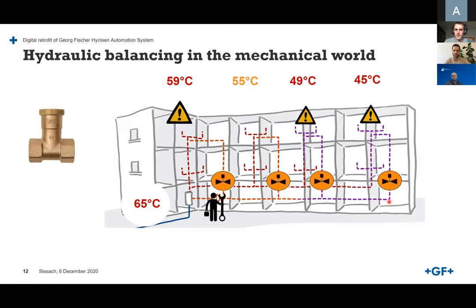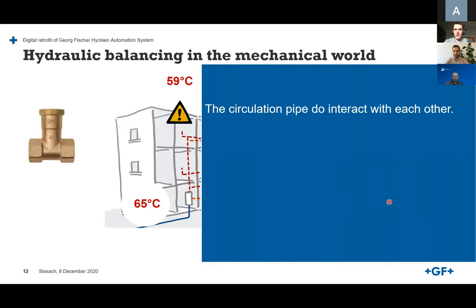So what are you doing? You call the plumber, he goes into the building and runs to every valve. Sometimes these circulation loops are not vertical, they are horizontal, so he needs to go up the stairs and go down the stairs. One main effect is if you change something on the first circulation loop, you will also change the water circulation of the other loops. So they influence each other. And this is one of the main points. Circulation pipes do interact with each other.